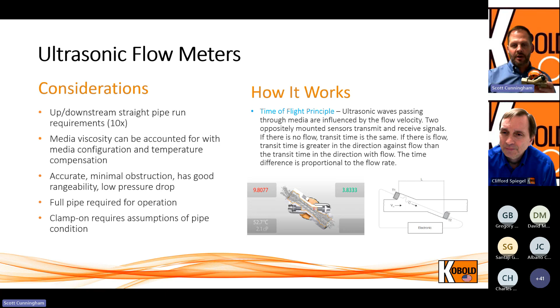That wraps up ultrasonic technology. Now we're going to talk about magnetic inductive. You'll see a lot of overlap here. With magnetic inductive, you don't have any moving parts, nothing like mechanical wheels or gears that can degrade over time. There are no maintenance costs associated with it, no upkeep, and no obstructions or restrictions that would cause a pressure drop.